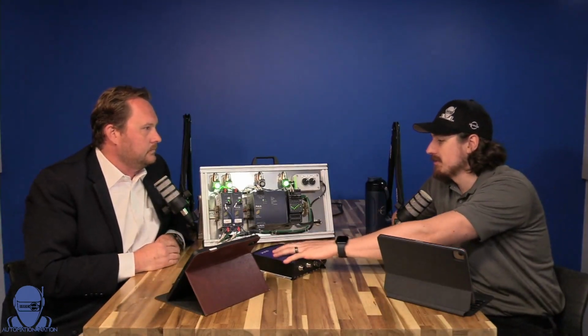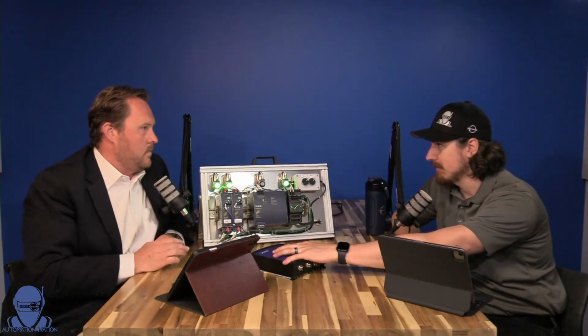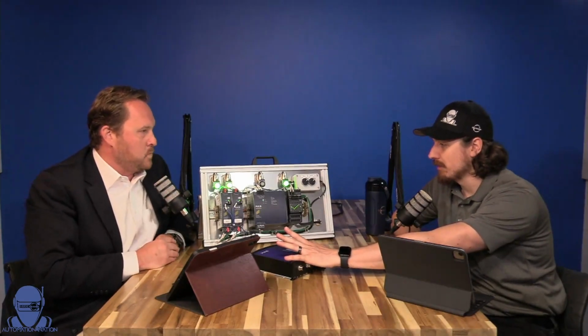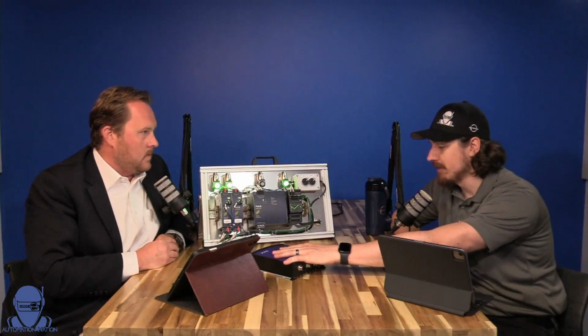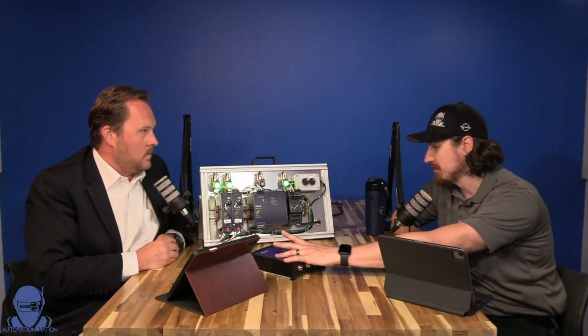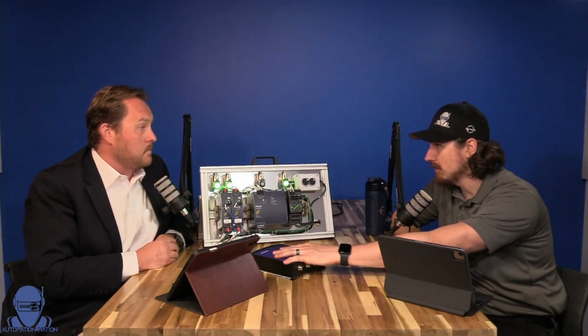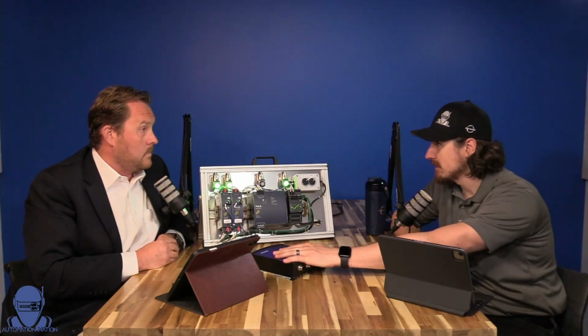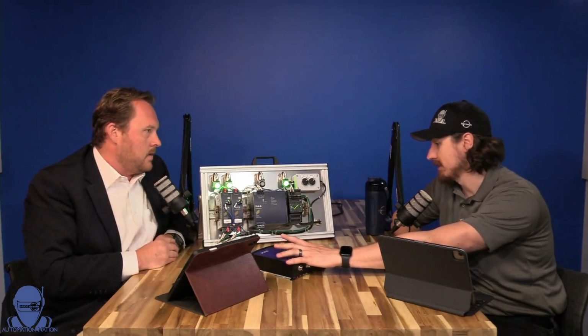But what are the cost centers that go into developing a remote control cabinet? This basically replaces a whole power distribution panel within reason. Everything is going on in here. You got rid of terminals that would be going between your circuit breakers and your incoming outgoing power. You got rid of, obviously, the panel itself, all the individual wiring, and other multiple mini components. If you wanted to monitor some of that, you'd have to have current or voltage monitoring sensors in there passing through. There's other things that this thing just completely removes in one piece.